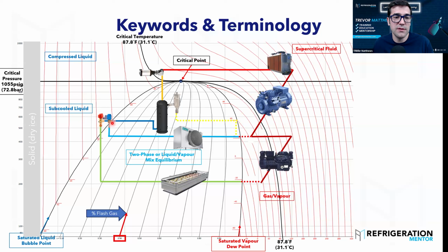What does that really mean? In this example, we must have a subcooler in here. We're pushing that out a little further. So when we drop our temperature down for our low temp to remove that heat, we are actually removing the proper amount of heat of that product that's in those display cases, coffin cases, as we can see here. And then we're taking it back to that booster compressor. That booster compressor is now compressing it and taking that heat and moving it into your transcritical compressor.